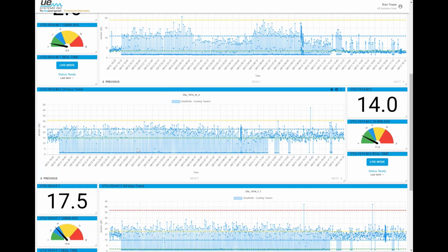We'll take a look at this bearing here. This is the motor outboard bearing of this cooling tower. Right now it's reading 14.0 decibels. I'll ask you to keep an eye on that, as it will change every minute as we go through this demonstration. That 14.0 decibels isn't very indicative unless you know what the baseline is. From this graph, the green line indicates that baseline value, which is set at 15. So right now I am reading very close to my baseline, which is a great thing.